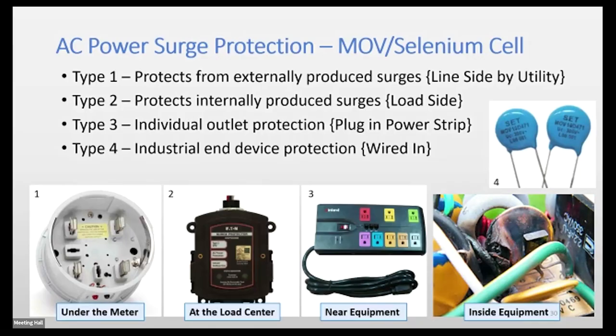I don't have that one. At the load center, they sell these at Lowe's and Home Depot. I have one installed in my house. It has to have its own breaker, I believe a 40 amp breaker, going into a double breaker, with wiring as short as possible. It fastens to your electric panel as close as possible to where your feed hits the disconnect, so it's a surge protector for the entire house. It goes right on the bus, you put a circuit breaker in for it. It's got lights that let you know if it's been hit and burned up the devices inside. Costs around $70 plus the breaker. I moved some breakers around on my panel to get enough space to install one.